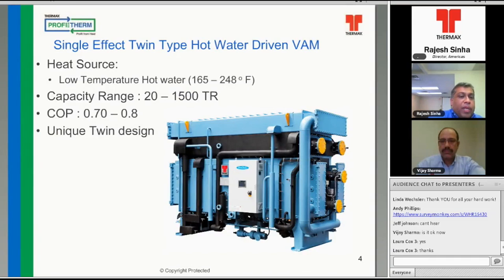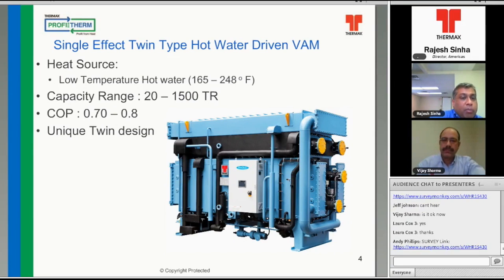Going on, we will very quickly look at the product ranges and what they look like and what the heat sources are. To begin with, the single effect type of hot water absorber has the heat source of low temperature hot water between 165 to 248 degrees Fahrenheit. This is available in a capacity range of 20 to 1500 tons, single units, and this has a COP of 0.7 to 0.8. And we deploy the unique twin type design, unique to Thermax, which ensures we can recover the maximum amount of heat from the available waste heat hot water source.